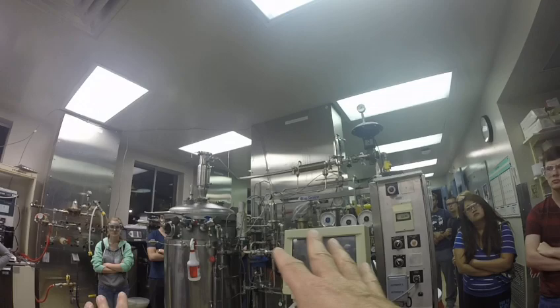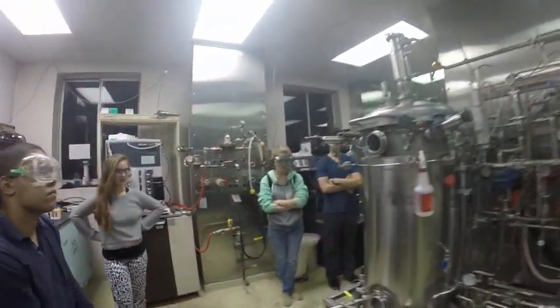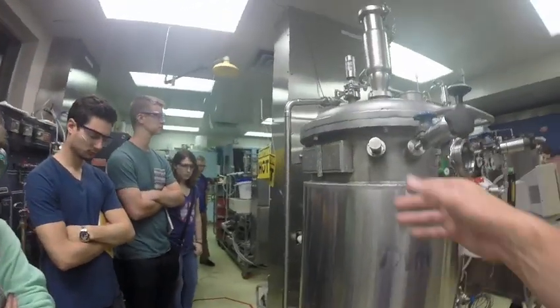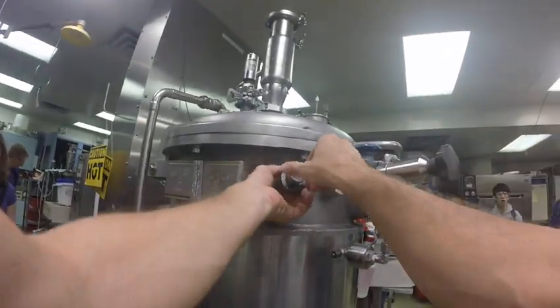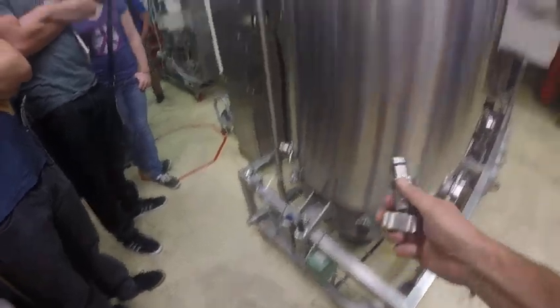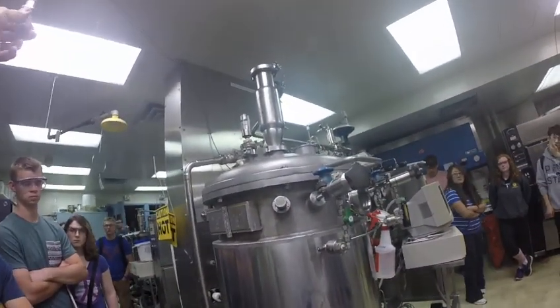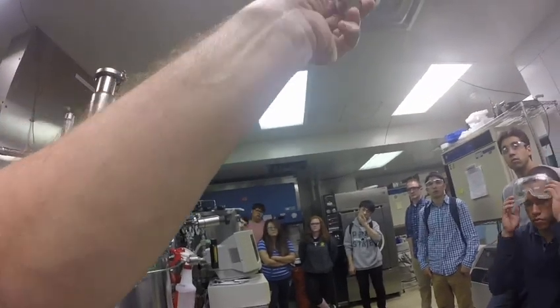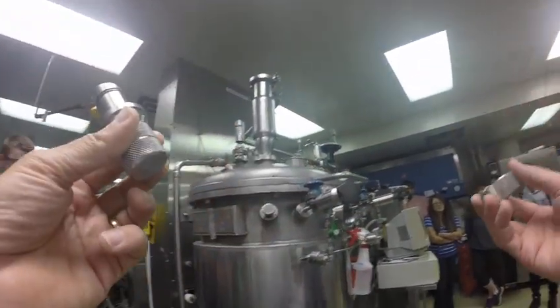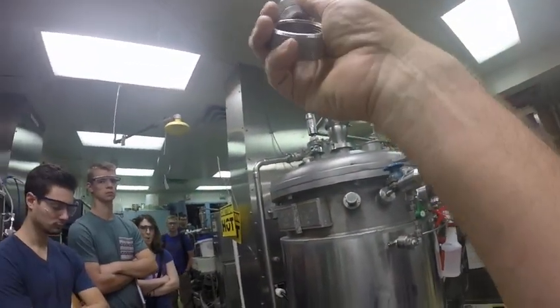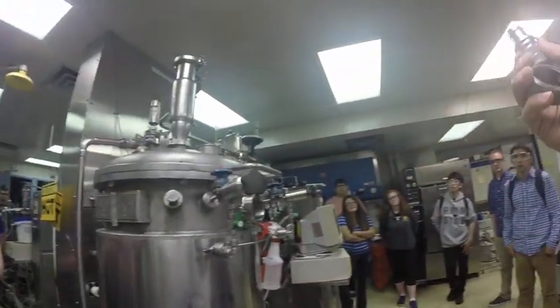The other aspect of these is that on the bottom of these units, you'll notice that there's a lot of these ports, and the ports are very, very similar. In fact, they're referred to affectionately as Ingold ports because somebody decided what it should look like. Who do you think it was? Ingold. Okay. And Ingold was a dominant manufacturer of probes for pH, dissolved oxygen, and so forth. And so they had essentially the industry standard for a 25 millimeter port.